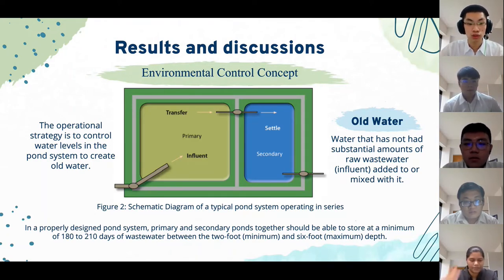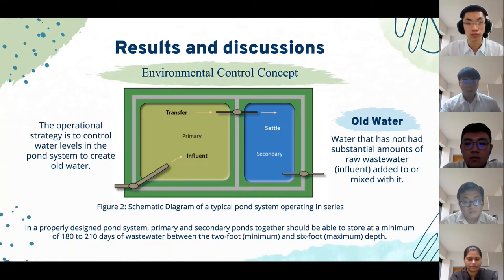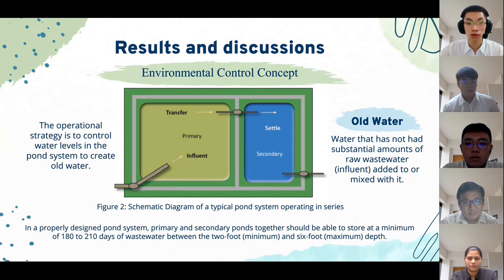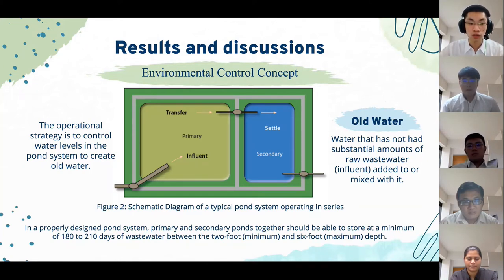The operational strategy is all about controlling water levels in the pond system to create 'old water' — water that has not had substantial amounts of raw wastewater added to or mixed with it. In a properly designed pond system, primary and secondary ponds together should be able to store a minimum of 180 to 210 days of wastewater, between a minimum of 2 feet and maximum of 6 feet depth. To improve the efficiency of creating old water, an example of a pond system operating in series, as shown in this slide, is applied.